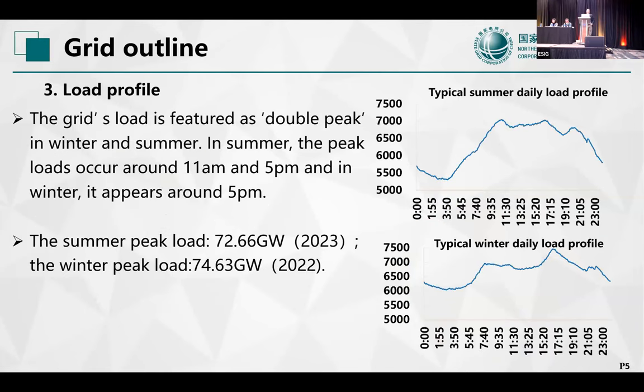And the grid load is featured as double peak in winter and summer. In summer, the peak loads occur around 11 a.m. and 5 p.m. And in winter, it appears around 5 p.m. The summer peak load is 72 gigawatt. The winter peak load, 74 gigawatt. And the right diagram shows the typical summer and winter daily load profile.